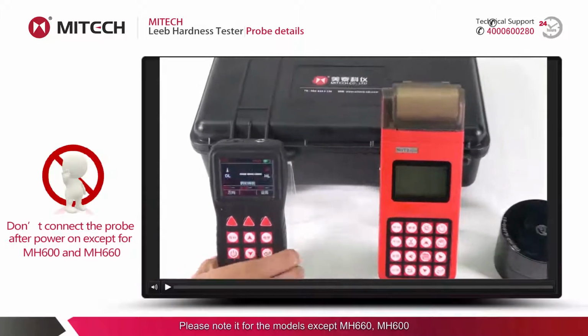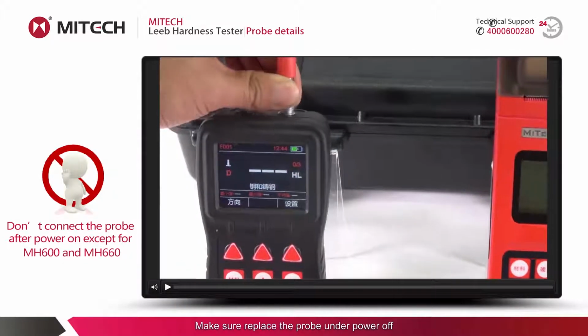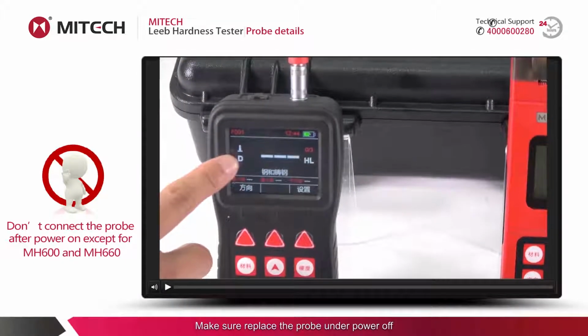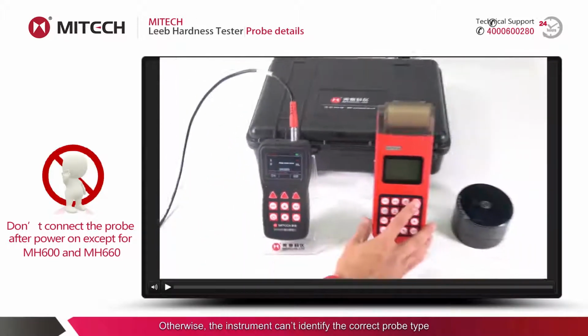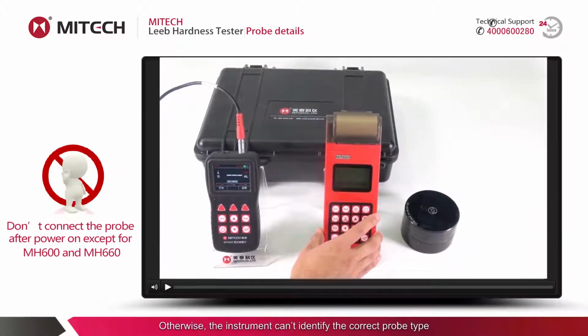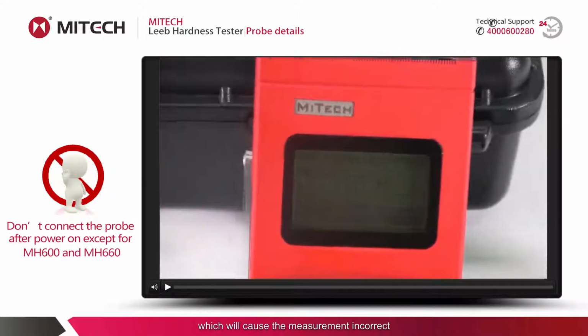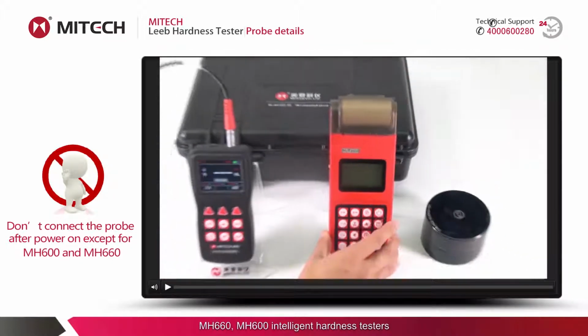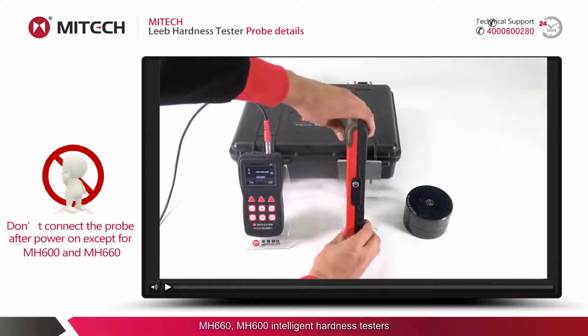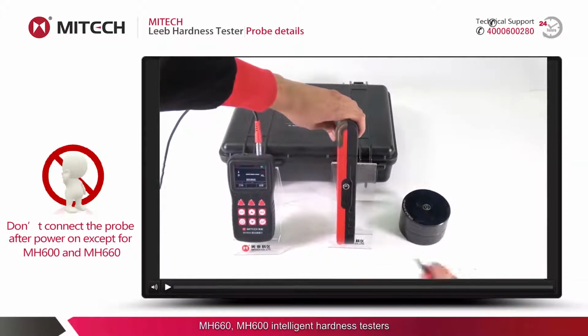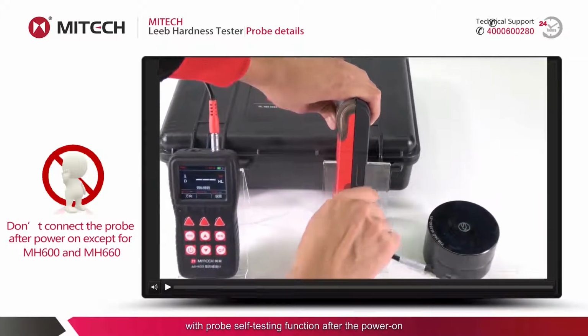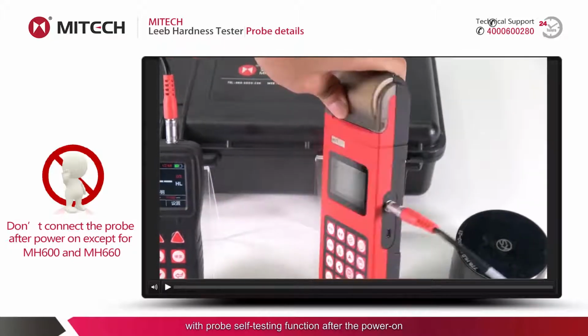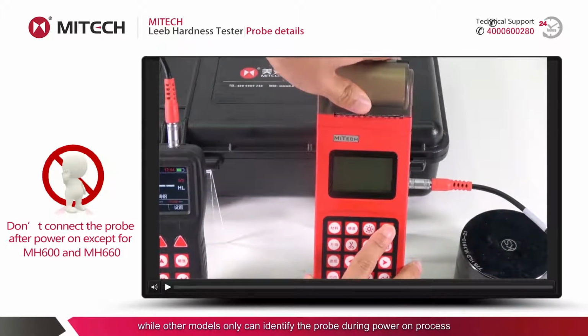First, connect the probe, then power on. Please note, for the models except the MH660 and MH600, make sure to replace the probe under power off. Otherwise, the instrument can't identify the correct probe type, which will cause the measurement to be incorrect.